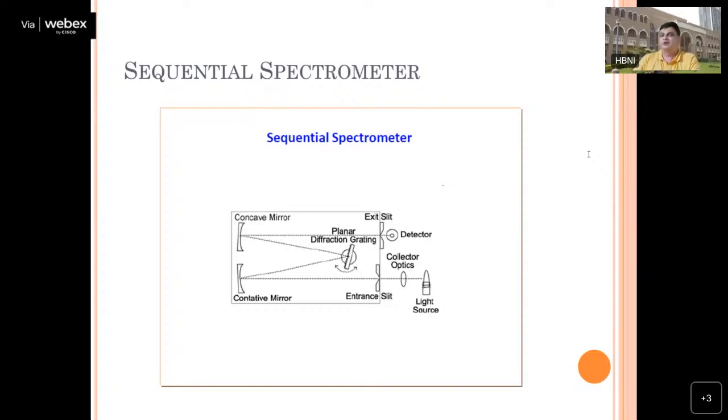And how do you come to know these interferences? See, once you are not getting a good calibration curve, that is how you will come to know, and you have to do those corrections. Sometimes you are looking for some concentration. For example, if you are measuring calcium and you know the concentration should be in the range of 5 ppm, but you are getting only 3 ppm, then you will look whether there is some sulfate or phosphate ions or not.